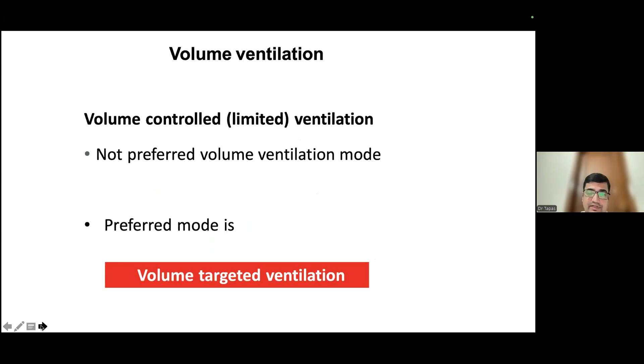This is a hybrid mode of ventilation. Volume targeted ventilation is basically a pressure control ventilation in which the microprocessor delivers the set tidal volume by varying the inspiratory pressure. So how does this happen? It happens through a dual loop mechanism. What are these two loops?